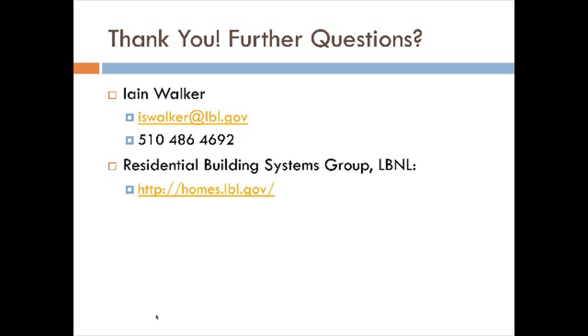Or you could have a simple manometer and a simple electric circuit to turn on a little red warning light that would be robust and would last for 20 years without any maintenance and so on. So I think a simpler approach is going to be better because it's more robust. And I think we're going to probably actually sense the pressure drop across the filter itself because it's more of a direct indicator, if you will, of the actual filter performance. And some of these things have been around for 50 years. We just don't use them very much right now. And maybe they're going to come back. We'll see.